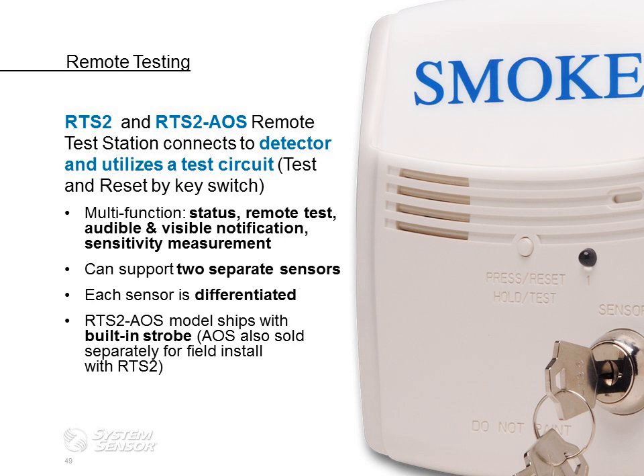Remote testing. The RTS2 and RTS2 AOS remote test station connects to the detector and utilizes a test circuit, test and reset by key switch. It's multifunction. It tells you the status, remote test, audible visible notification, and sensitivity measurement. This is the Cadillac of remote alarm indication and test products. This meets all the code requirements for remote annunciation, indication, testing, reset, as well as allowing the field personnel ease of testing because they don't have to get to the actual unit. They can do everything from the floor.